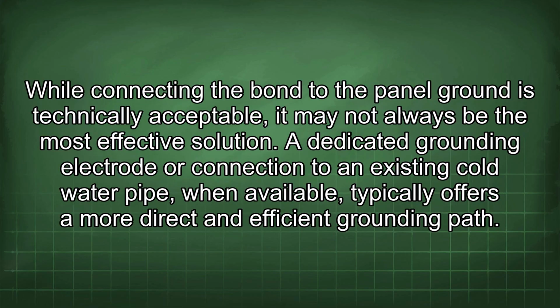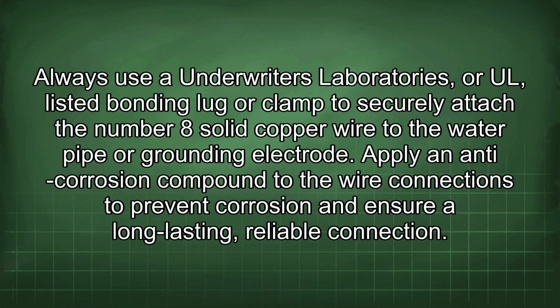While connecting the bond to the panel ground is technically acceptable, it may not always be the most effective solution. A dedicated grounding electrode or connection to an existing cold water pipe, when available, typically offers a more direct and efficient grounding path. Always use an Underwriters Laboratories or UL listed bonding lug or clamp to securely attach the number 8 solid copper wire to the water pipe or grounding electrode. Apply an anti-corrosion compound to the wire connections to prevent corrosion and ensure a long-lasting, reliable connection.